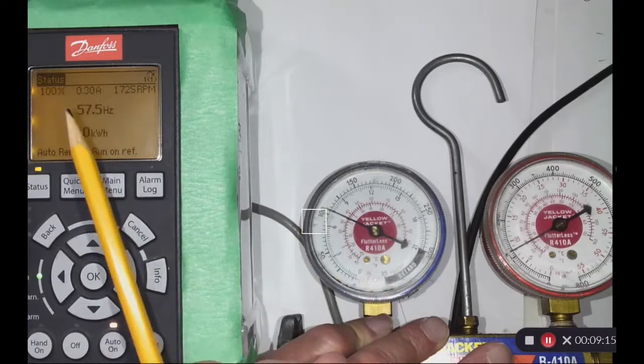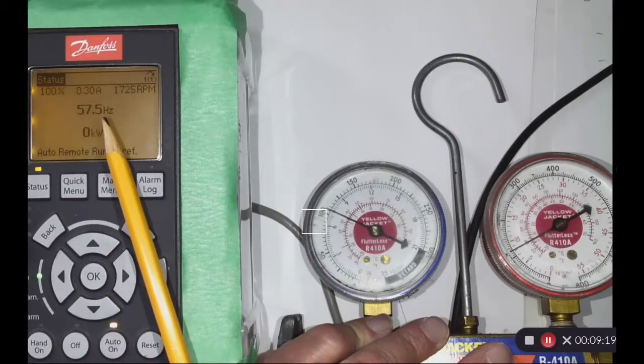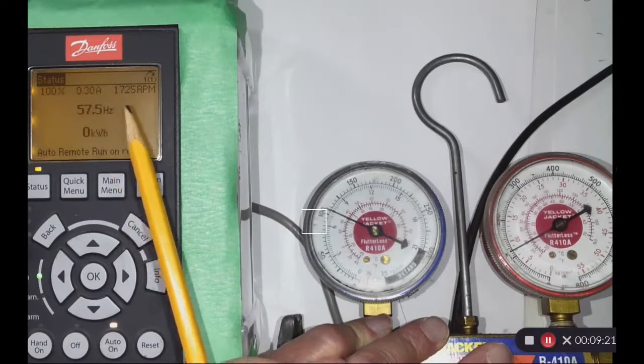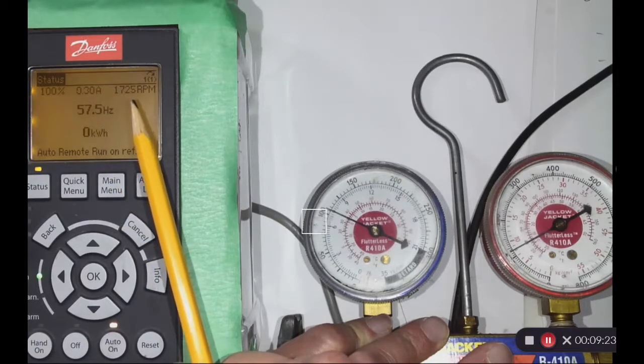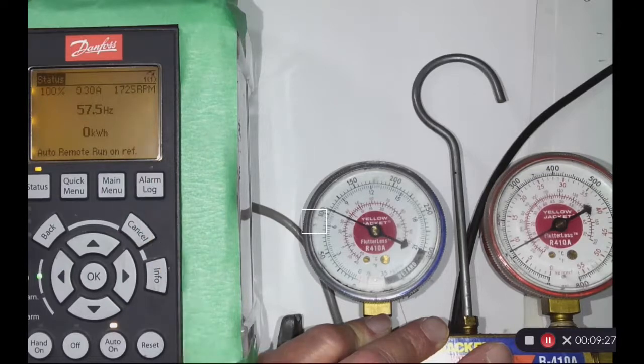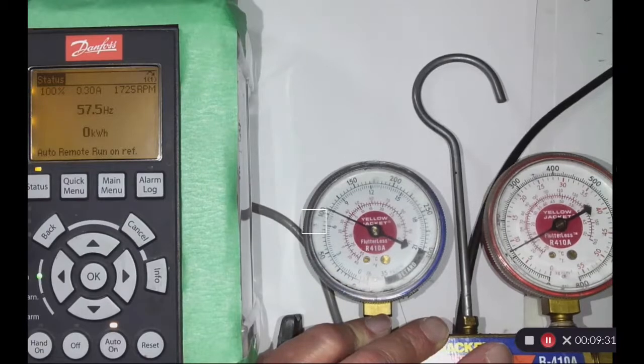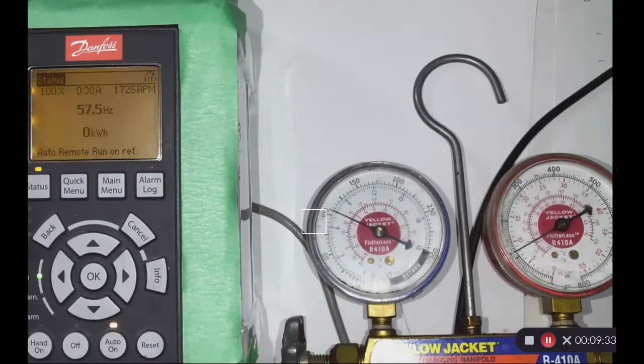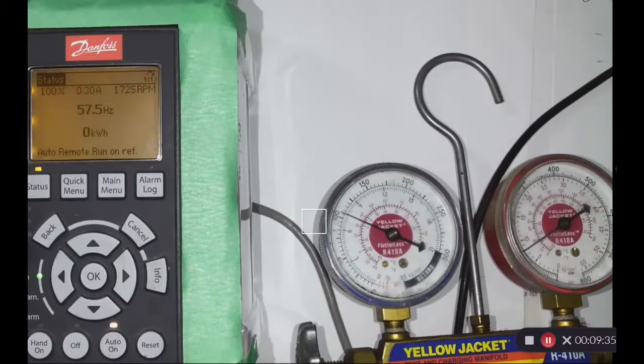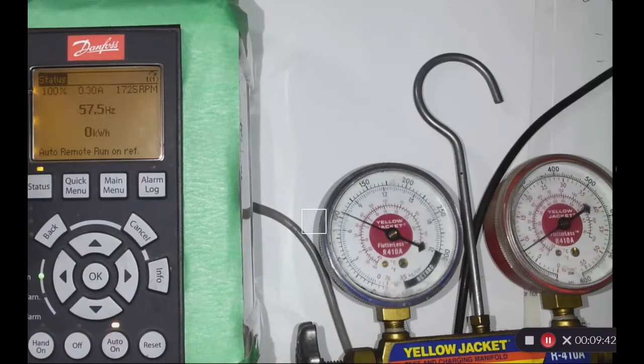you can see on my LCP, I'm up at 100%. I'm almost topping out at 57.5 hertz. And I've set the maximum RPM in the limits to 1725. And that's what it's turning at. So I'll just close off the gas pressure to the low side from the high side. And then slowly bleed this down. I need more hands here. And watch here at my status as to my percentage of the full scale.